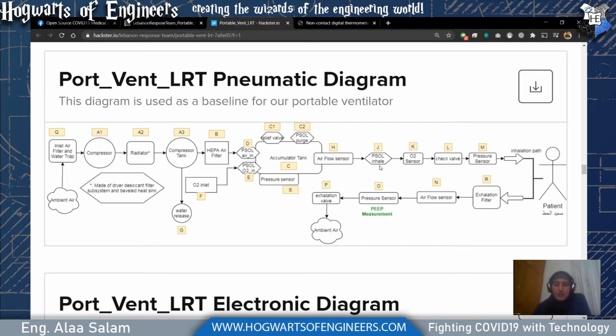The O2 sensor K will observe if the percentage of oxygen that we set at level E is the same amount that is reaching the patient. Now, check valves L and the pressure sensor M will not interfere in the level of oxygen being measured on level K. So it's okay to have extra sensors or extra valves after it. That's why we put it over here on this end.